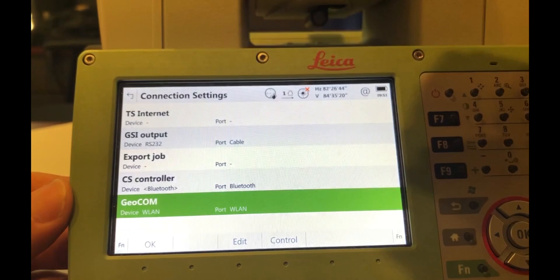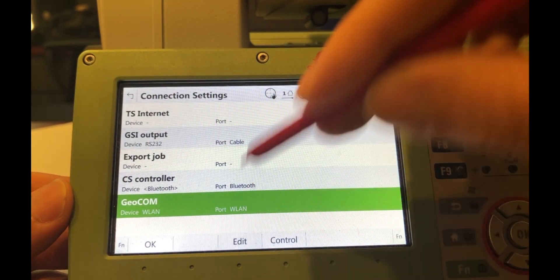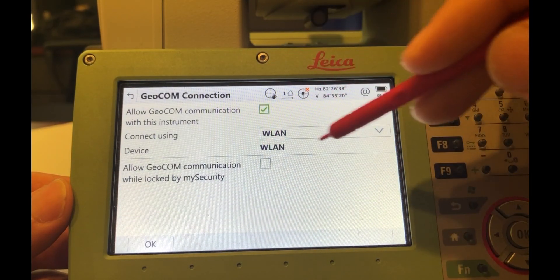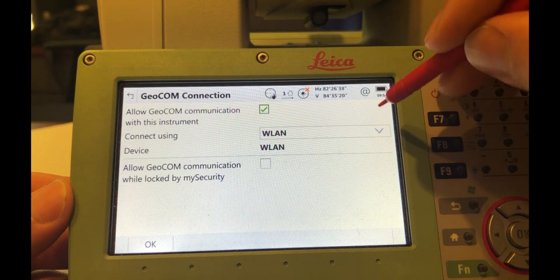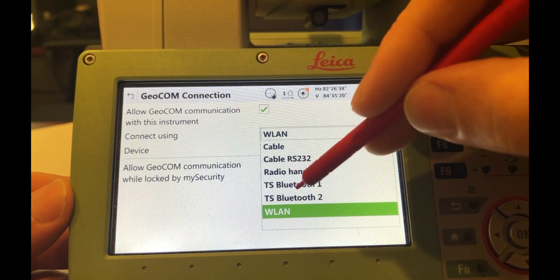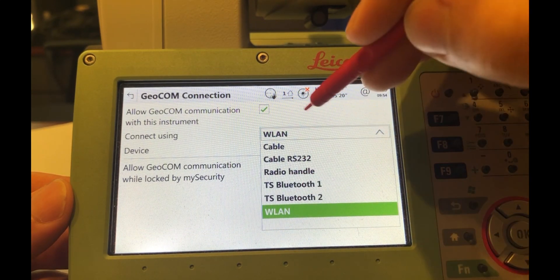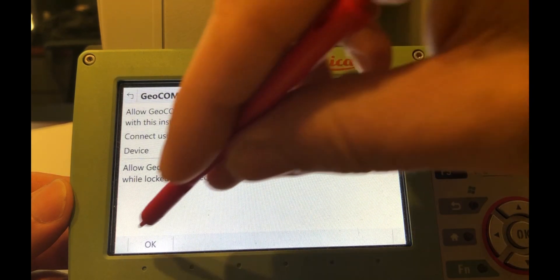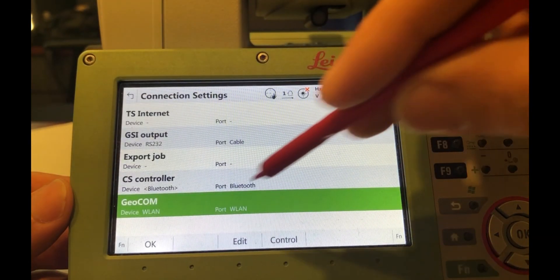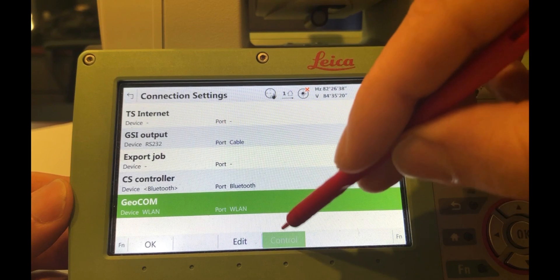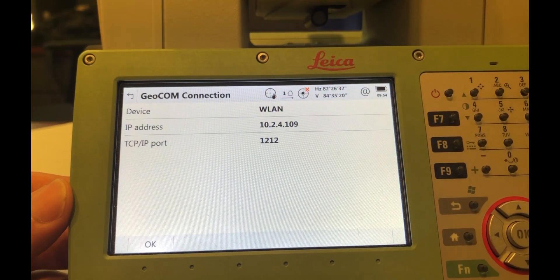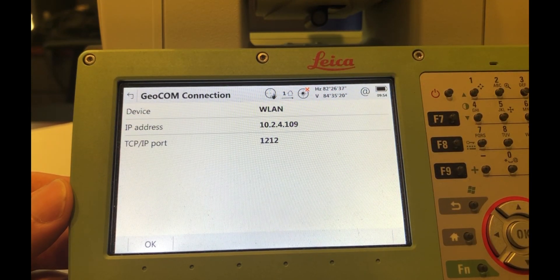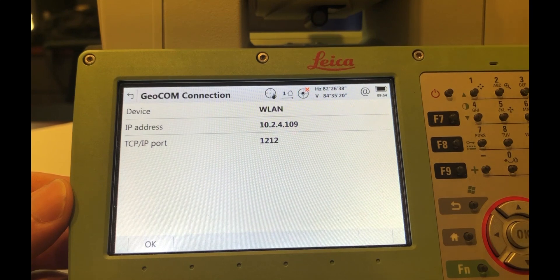Go to the Geocom settings and hit Edit, and you'll see it's got the wireless LAN connection. This is where you change it if you were using Bluetooth or a cable connection, but in this case we want Wi-Fi. And you also have direct access, if you hit the Control button, to getting the IP address. So that's the IP address that you will enter in SA when you go to Connect.